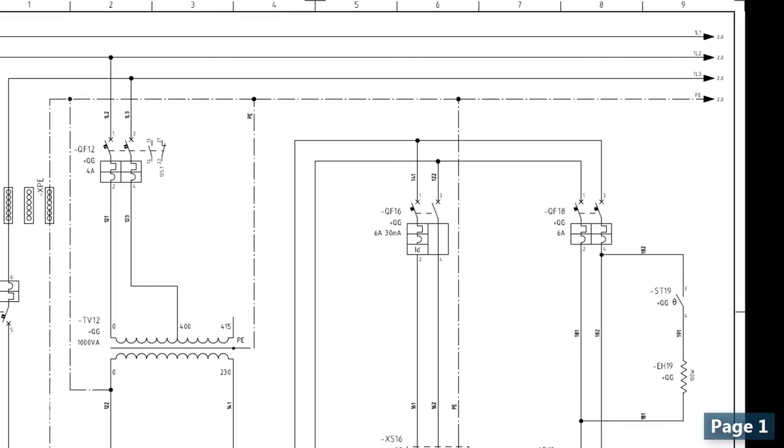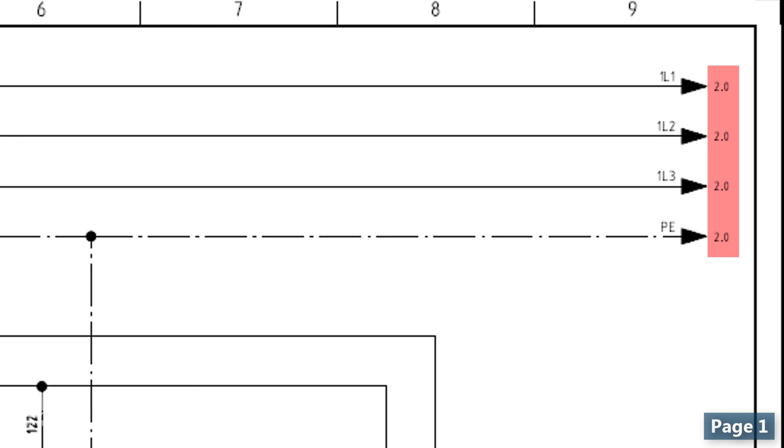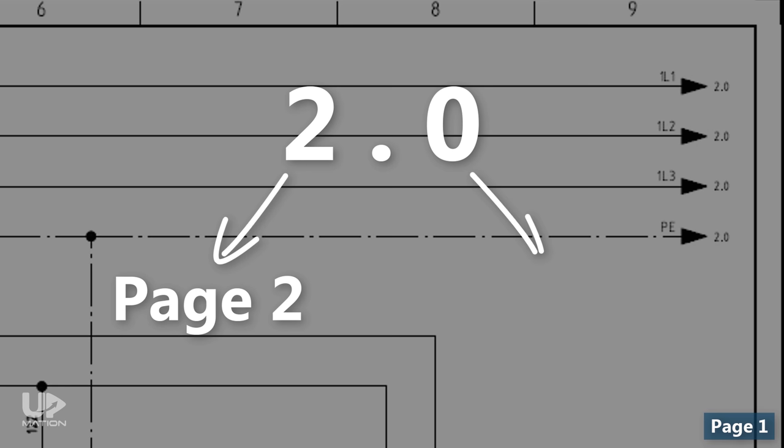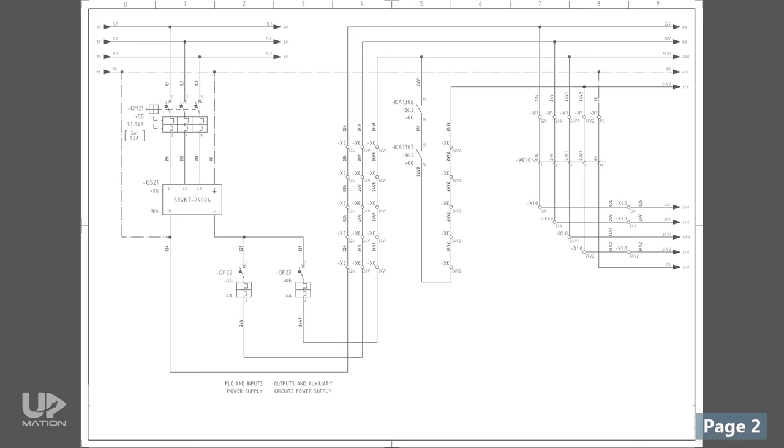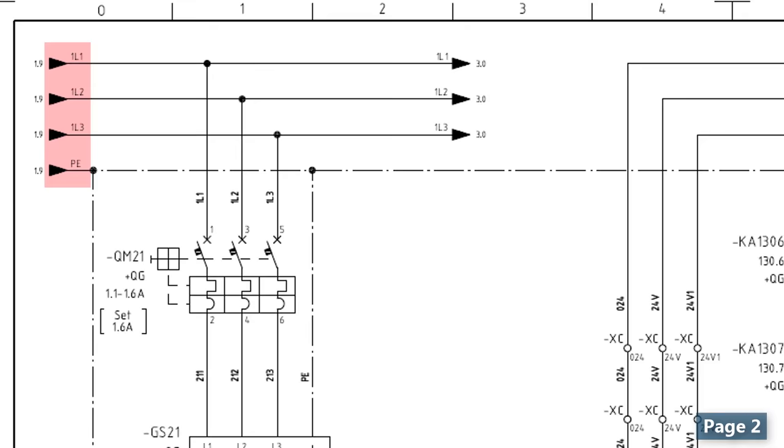Let me explain it by some examples. For instance, the main three-phase power is shown with some arrows and numbers on top of the page. All of them have a 2.0 number just beside the arrow. By 2 it refers us to page 2 and by 0 it points out to the first column of page 2. And there you go, it's our power source on page 2.